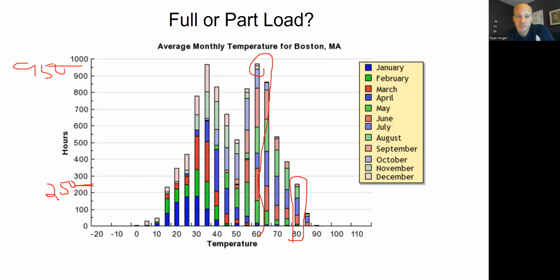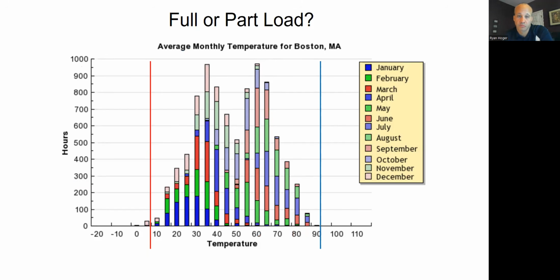So the systems that we have, whether it's VRF, heat pump, non-heat pump, whatever, these kind of systems were typically designed for certain outdoor conditions, right? Every cooling system is designed and tested and rated by the manufacturer and AHRI at 95 degrees outdoor air temperature, right? But in Boston, how often are you at 95 degrees? Hardly ever. It's like a little sliver. I can't even barely see it on the line. It's like X amount of hours a year, single digits typically, unless it's a freak year, right? By the way, this data on this screen is a 30-year rolling data kind of thing. All right, so you're not spending a lot of time there.